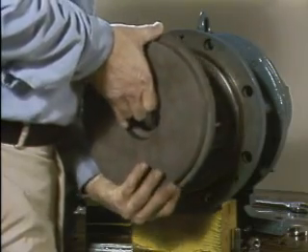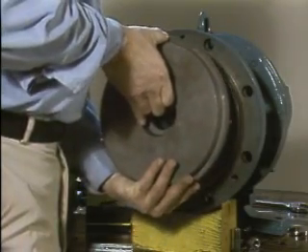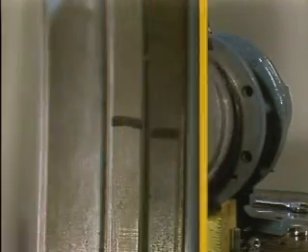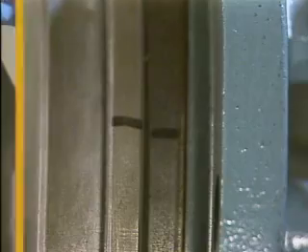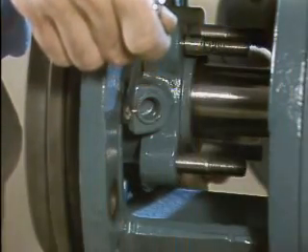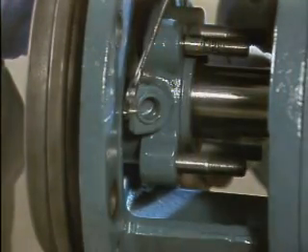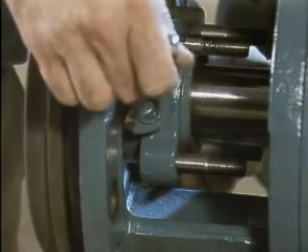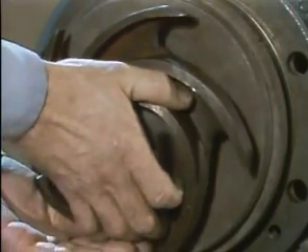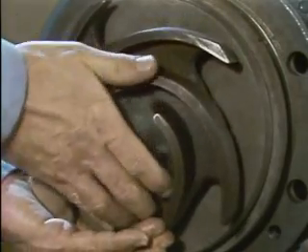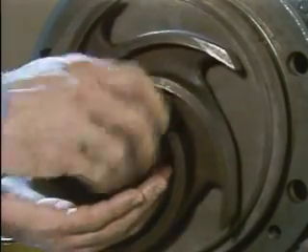After the sleeve is in place, the pump backplate is positioned onto the frame. The match marks on the backplate and the frame are checked to make sure that the backplate is properly aligned. Once the backplate is in place, the nuts that hold it onto the frame should be tightened evenly. Next, the impeller, which holds the sleeve in place, is installed. Then the clearance between the impeller and the backplate will need to be measured.